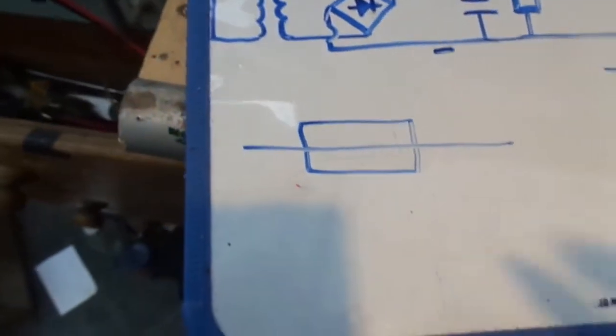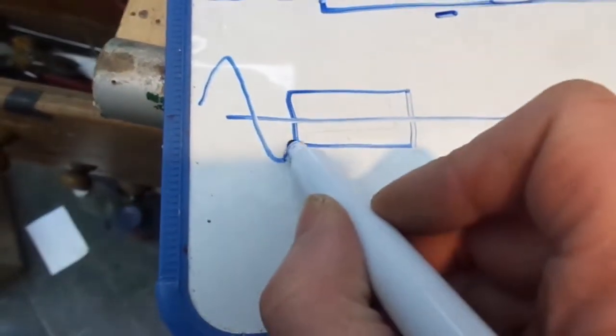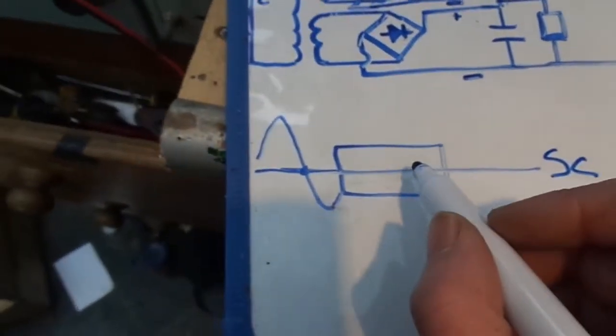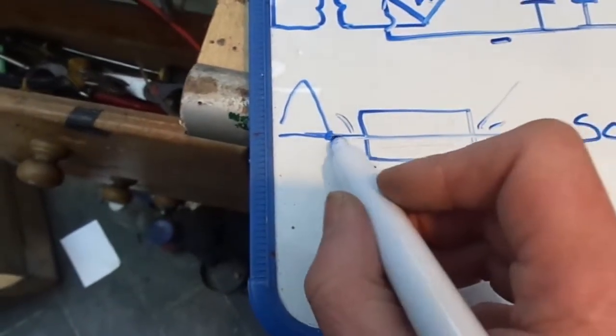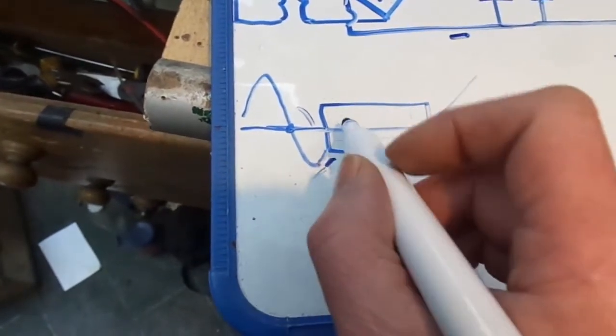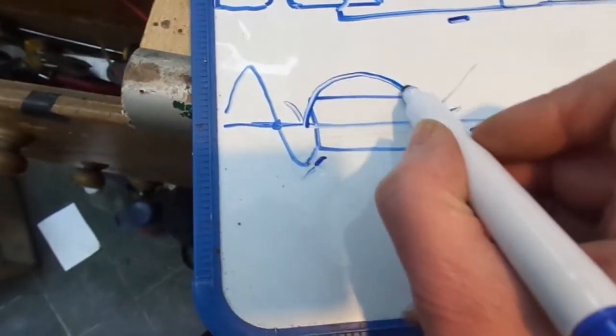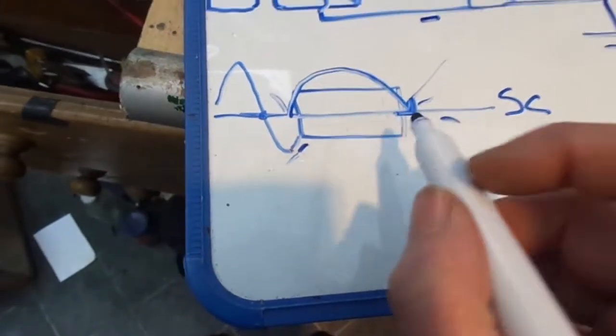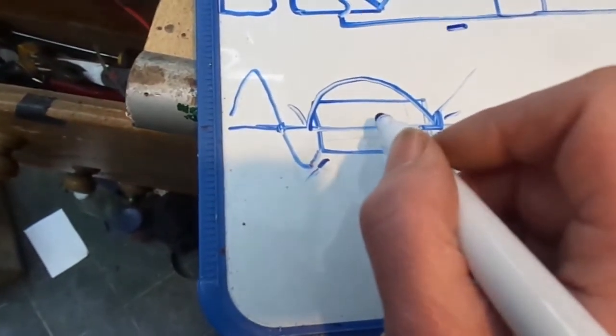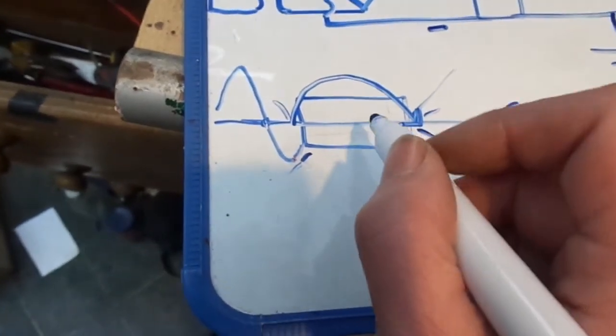There's your AC fuse. Here it comes there, but you see here if this is our midway point, it's dropping to 0 volts. So if we get a short circuit here and the fuse blows, because that drops to 0 volts, any arc, because remember if we've got a high voltage here, the voltage wants to jump over over to there, and there probably will be an arc. So any arc we will get, because it's AC and it drops to 0 volts, the arc will extinguish more readily than if it is DC.